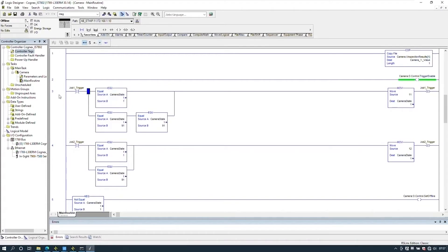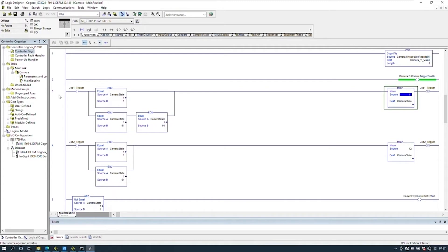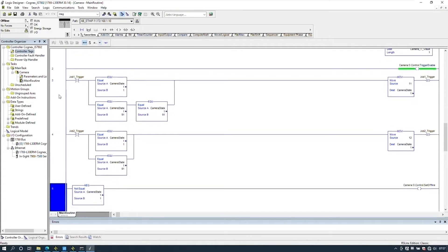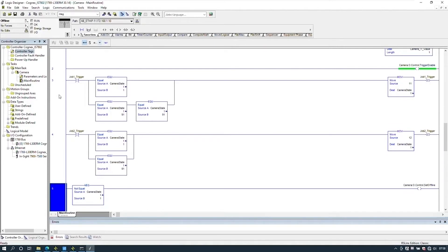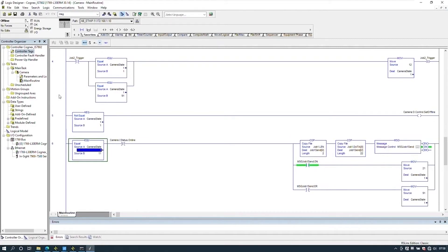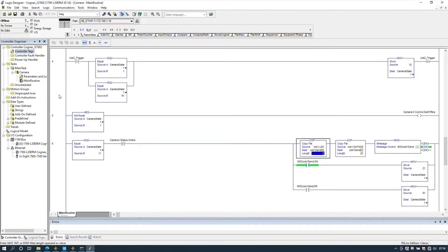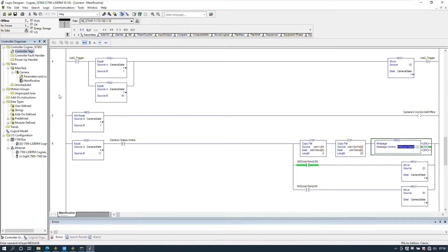Back in the PLC code we are executing a state routine that makes sure everything happens in order. If we trigger a job change and we are in state 1 or fault state 91, then it allows the program to move to state 11 and unlatch the trigger. Whenever we are not in state 1, we always set the camera to offline ready to receive a job change. As we are in state 11 and it has confirmed the camera is offline, we prepare the data to send to the camera. Our ASCII string varies in length, so we put the number of characters into the first two bytes of the array. We then take 22 characters of ASCII and put them in the following 22 bytes. We then trigger the message — once done we move to state 21, or if the message block errors it moves to state 91.